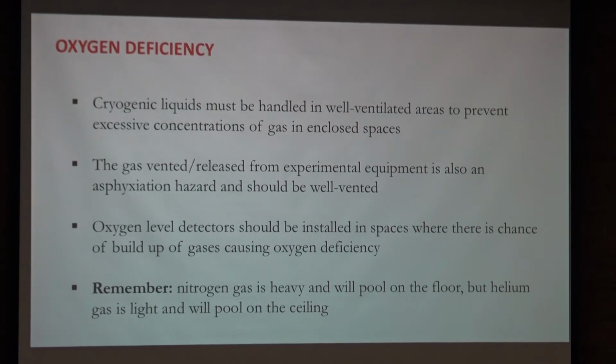oxygen level detectors. One thing to keep in mind: the most common cryogenic liquid, liquid nitrogen, is heavier than air, so it will accumulate close to the floor. So you want to basically keep breathing above floor level. Liquid helium is the opposite. It is lighter than air, so it will start filling the room from the ceiling. So keep in mind which cryogens you're using, how they accumulate, and where you want to ventilate them out of your laboratory.